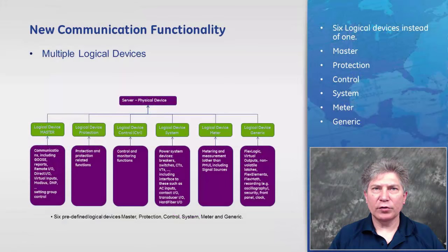There are six logical devices now: master, protection, control, system, metering, and general. The master contains the communications including GOOSE, reports, remote I/O, direct I/O, virtual inputs, Modbus, DNP, and so on. The protection controls just that, all the protection functions. The control contains control and monitoring functions.